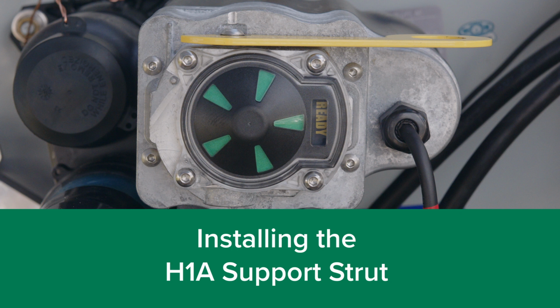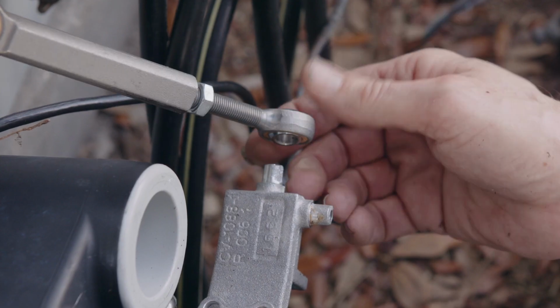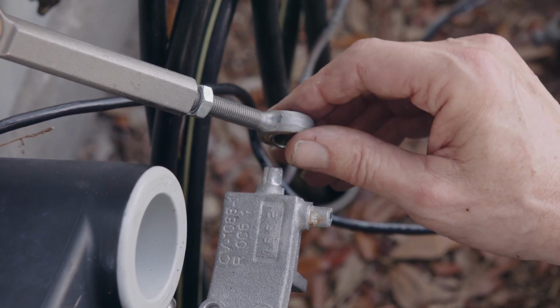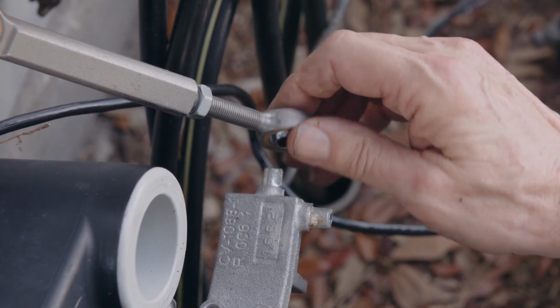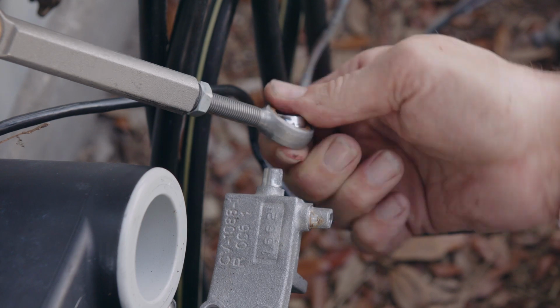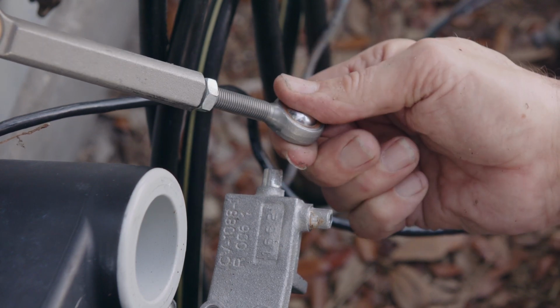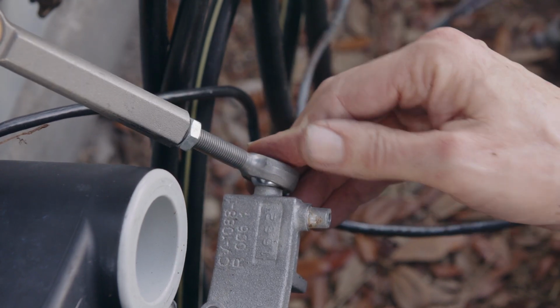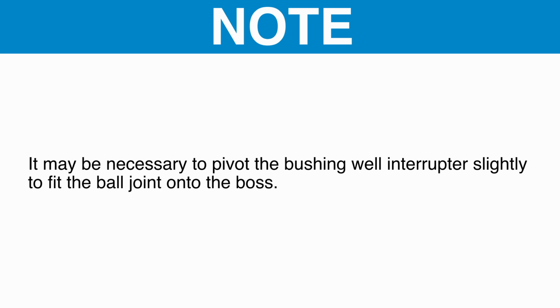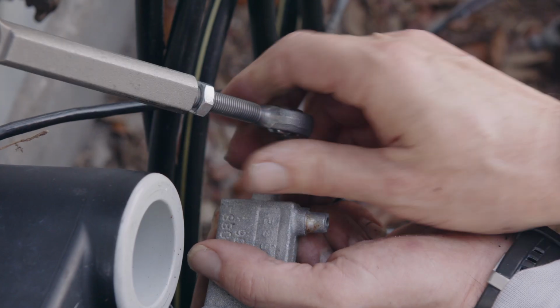To install the H1A support strut. Step 1. Adjust the length of the H1A adjustable link until the ball joint just fits onto the boss on the H1A bushing well interrupter bracket. Do not install it. Note: it may be necessary to pivot the bushing well interrupter slightly to fit the ball joint onto the boss.